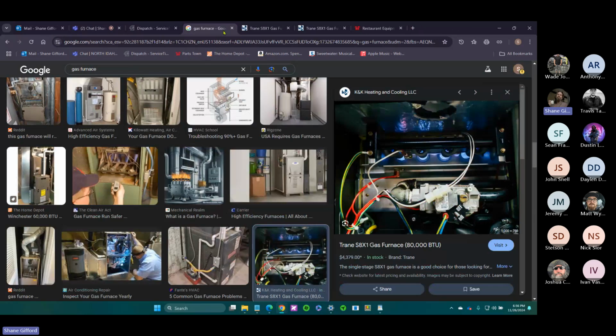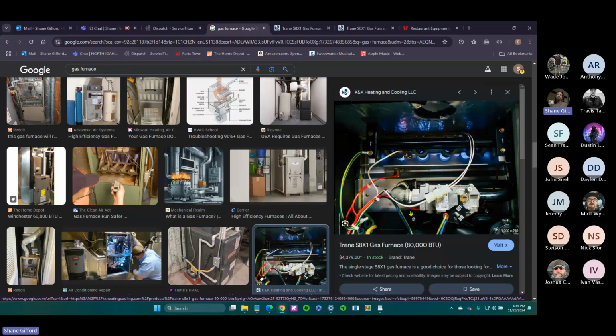Oh, don't make me call on somebody. Let's see. All right, I'll start you out. First, inducer. Then when your inducer activates, it goes through your inducer pressure, and then igniter, gas valve, and then flame sensor. There you go. So all gas-fired appliances have a particular sequence of operation to ensure that everything is safe before we allow fire to take place, right?